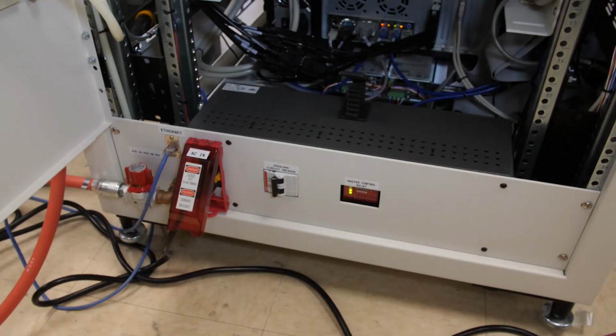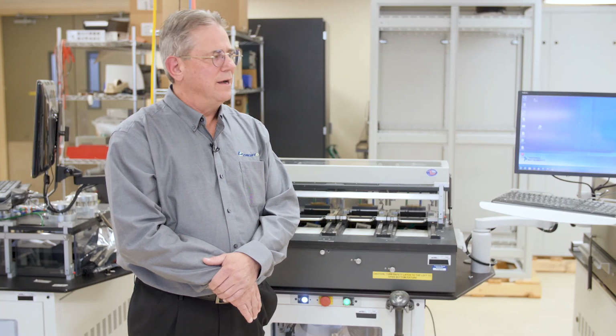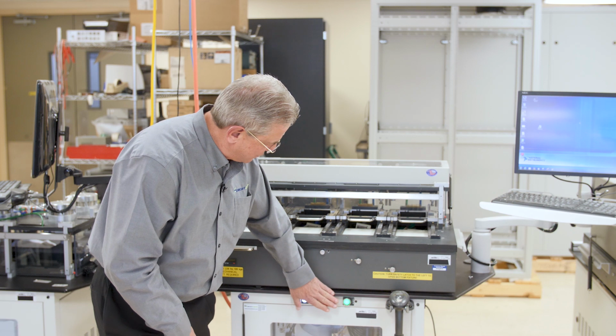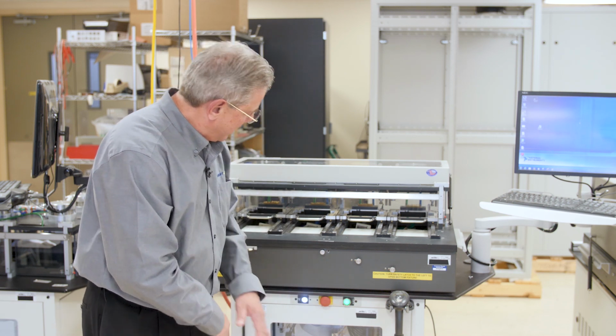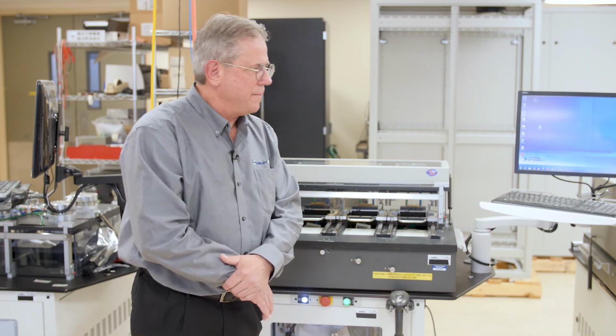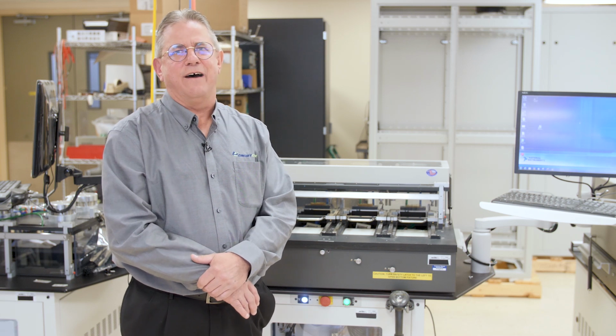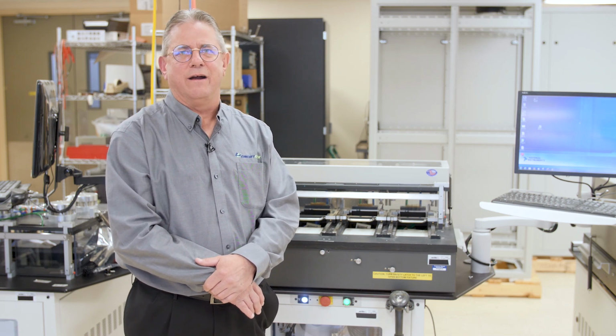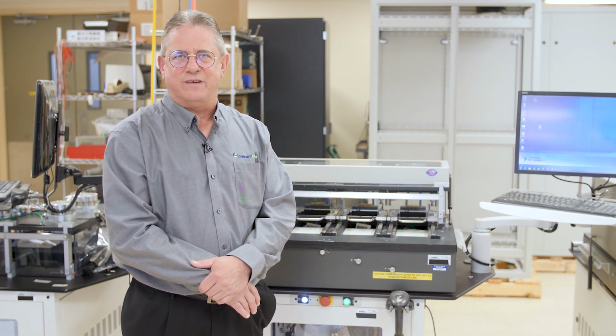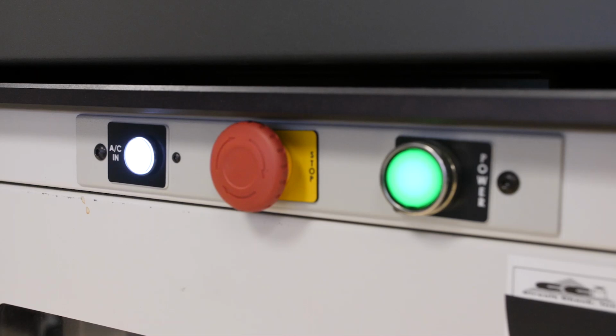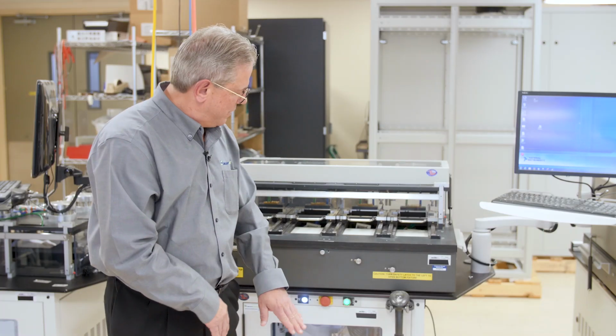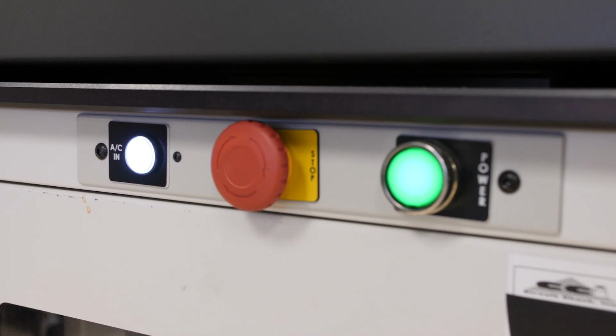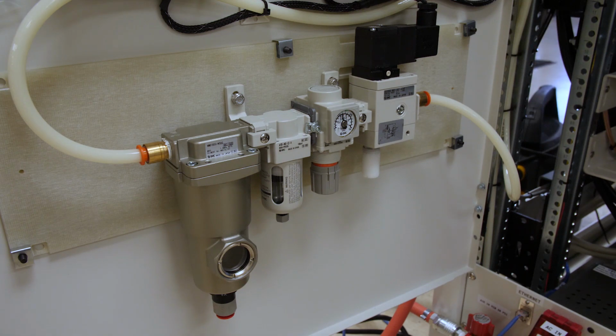The other thing to consider with these racks is your safety considerations. In this case, you see there's an e-stop, and also some lamps here. You should have a power distribution unit in there, which contains a safety switch and also some contactors. When you hit this switch, you want to see both legs of power turned off. You also want to see your air go through a dump valve and disable that.